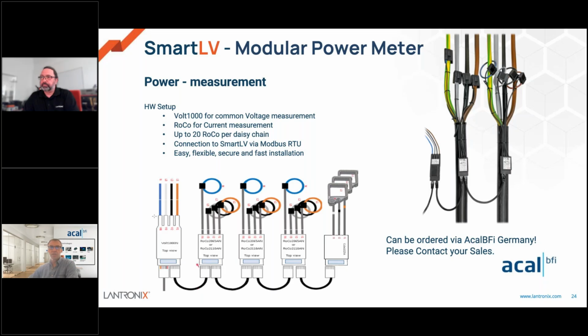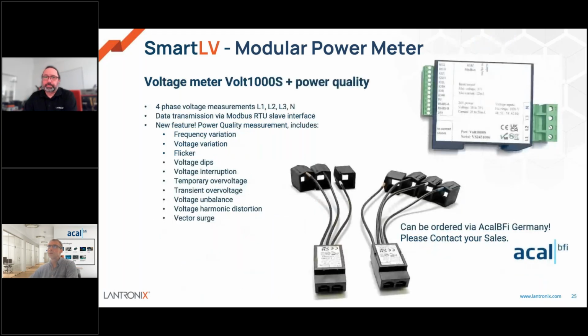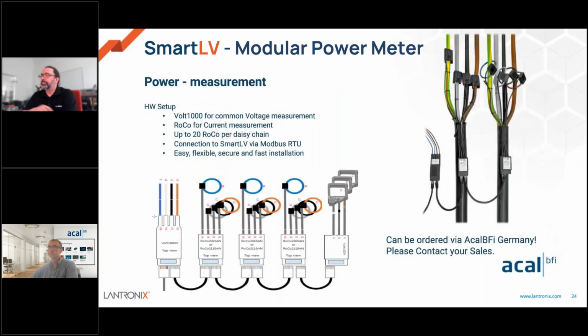We offer some variations of the current modules. Now, keep the previous slide, please, Guido. Yeah. Our so-called ROCOS current sensors with the Rogowski coils are available in two versions. One with a 65 mm diameter coil and the other version with a 110 mm diameter coil. The other current sensor model, called Cube, has a different form factor and is designed for cables where the distance between the cables is as low as 4 mm. This is what you see on the right.